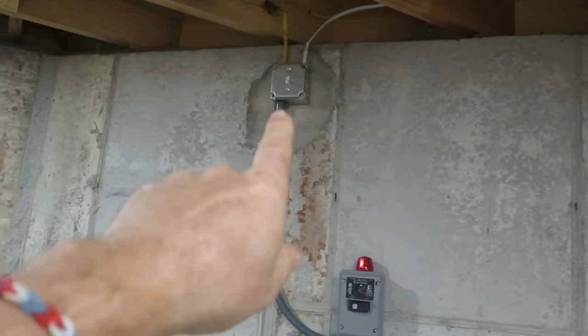So what we have is the power coming into that box through the wall, and the main is being fed by that yellow 12-2 line, and the separate 14-2 line is what's running the alarm. They can't be on the same circuit. So if the breaker kicks on the main pump, that's a separate circuit, so the alarm will sound. I'm assuming it's both a light and that red light flashes, plus I'm assuming it whistles or has some type of alarm sound. Don't want to hear it, but that's what that looks like.